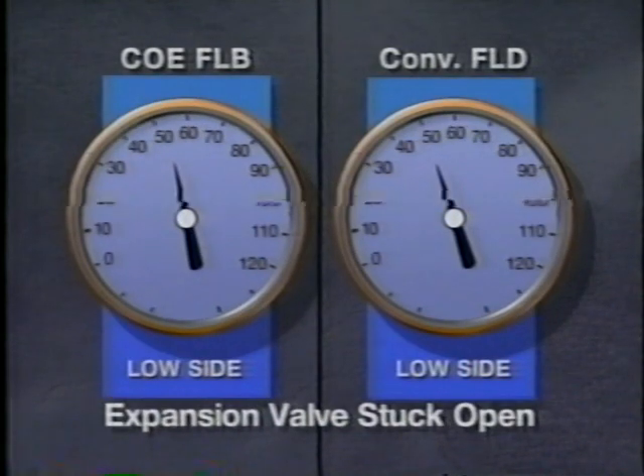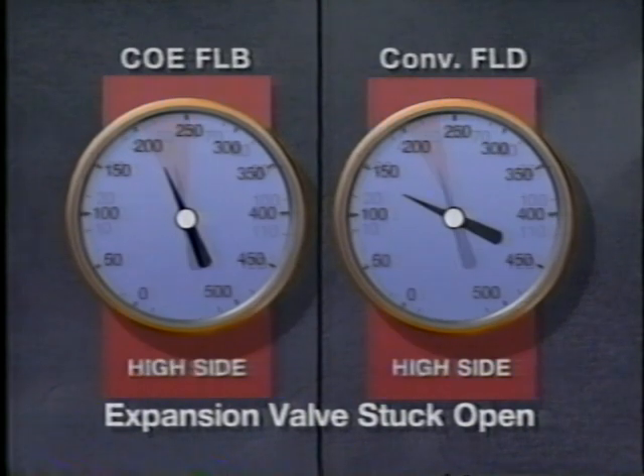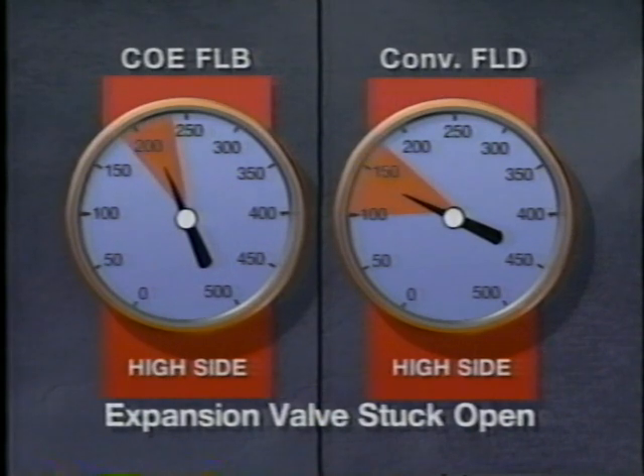If the expansion valve is stuck open, causing flooding of the evaporator coil, the suction pressure will be high, while discharge pressure will be low. The expansion valve must be replaced.